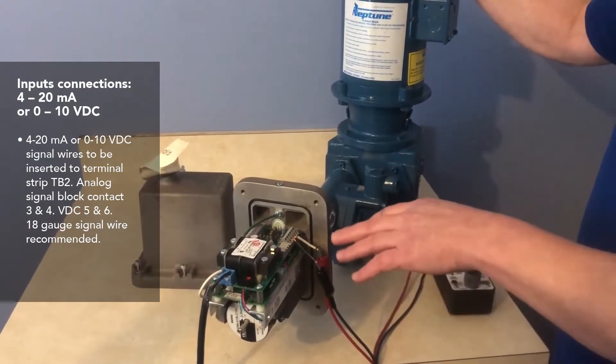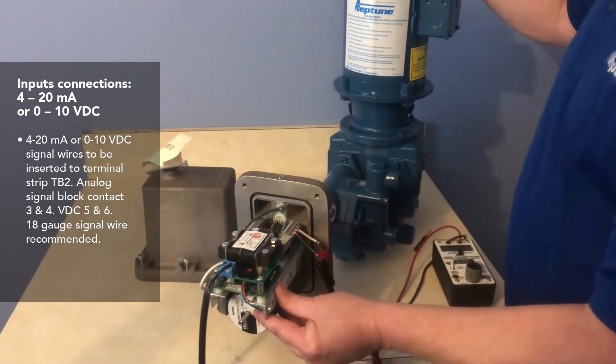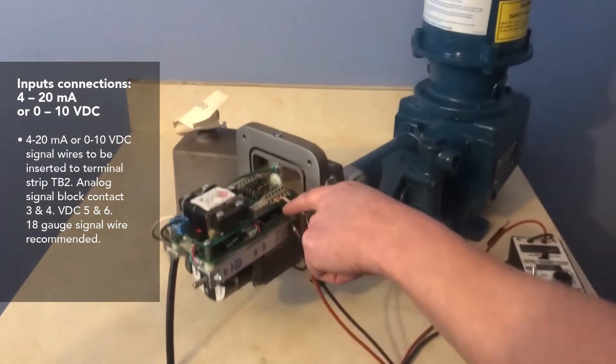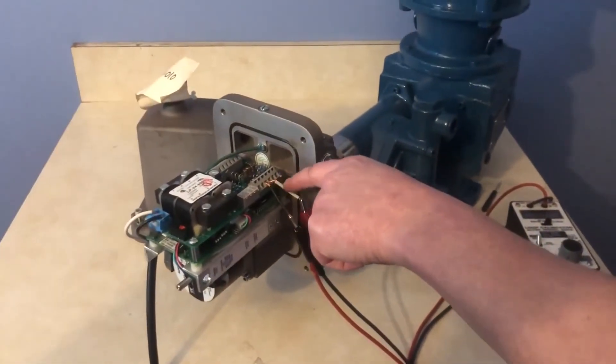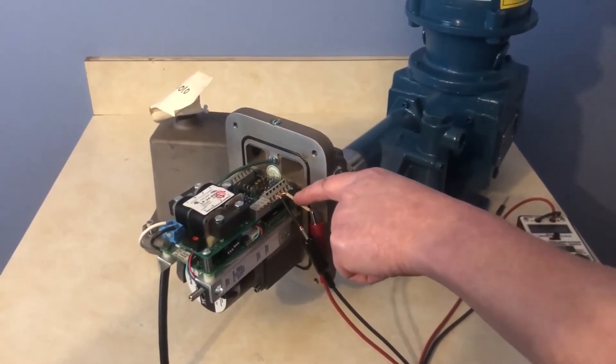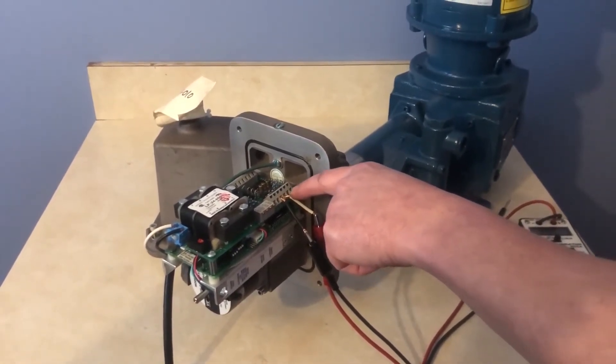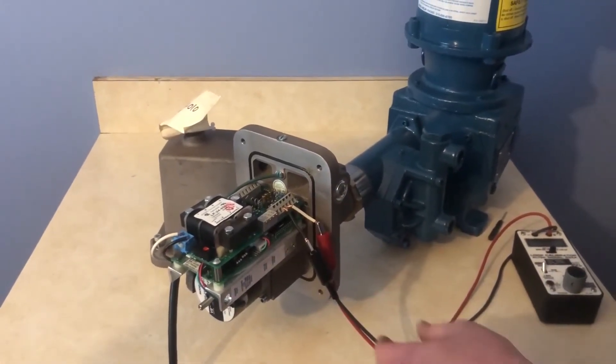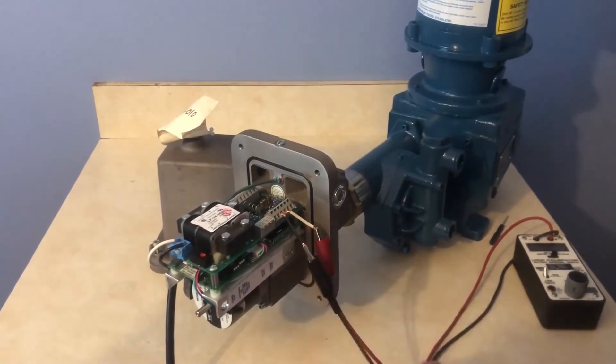Secondly is your current connections, which is on terminal block TB2. Connectors three and four are for the analog, but there is an optional voltage connection on five and six. We're going to be using analog today because that's a majority of what the customers use.